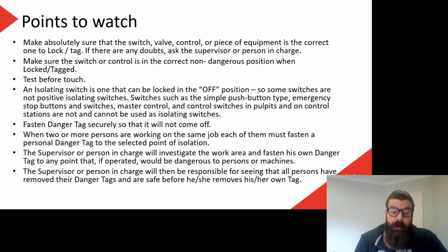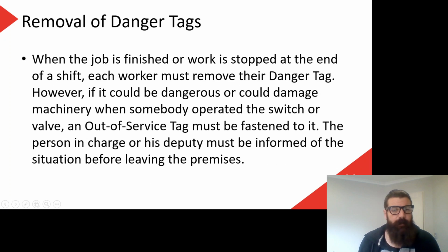The supervisor or person in charge will investigate the work area and fasten his own danger tag to any point that, if operated, would be dangerous to persons or machines. So the supervisor might also put a danger tag on even if they're not working on it themselves, and in that case they would probably be the last person to take their tag off. The supervisor or person in charge would then be responsible for seeing that all people have removed their tags and are safe before they remove their tag. So as I just said, they would be the last one taking the tag off.